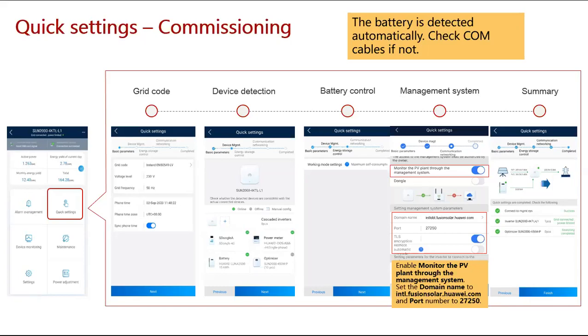For commissioning the device, once you enter the device, click quick settings. A new window will pop up asking you to set the grid code. You need to set the appropriate grid code for the UK, which is United Kingdom G98, so click on that one.